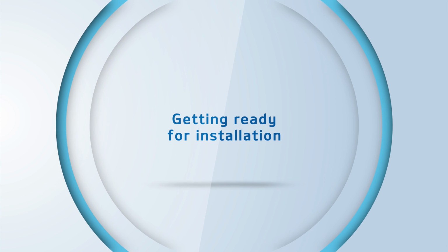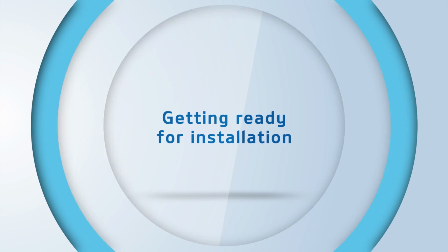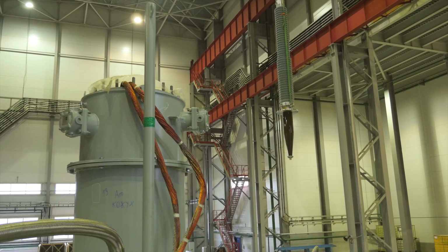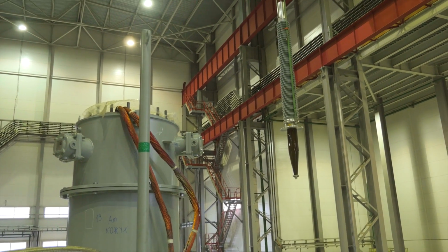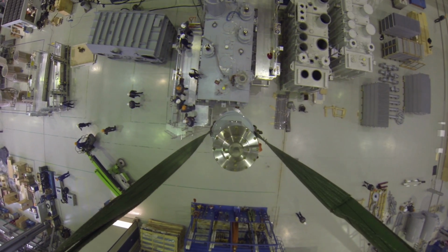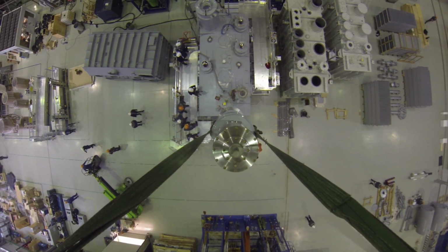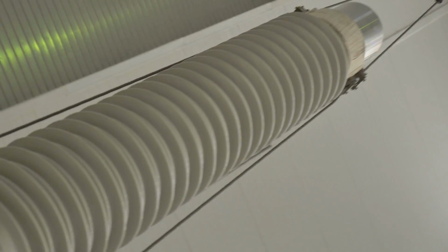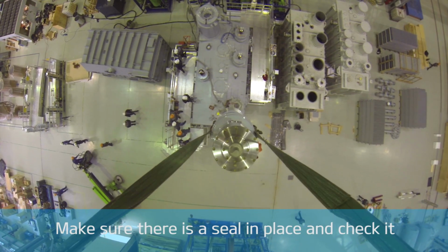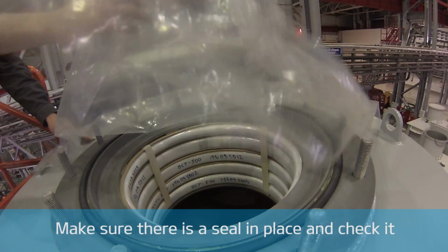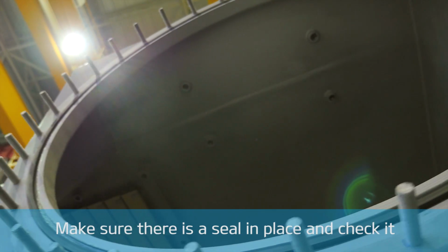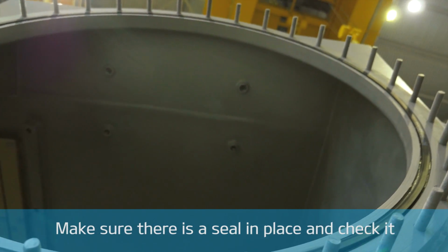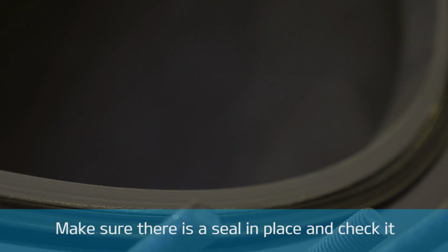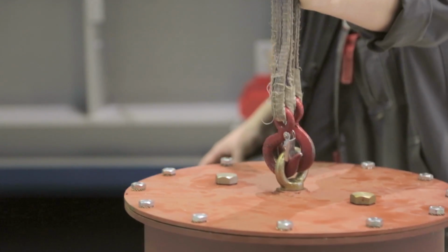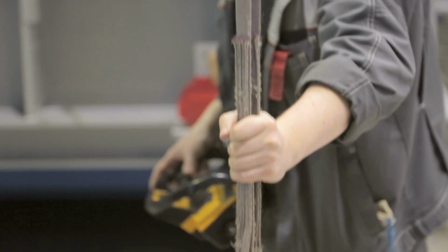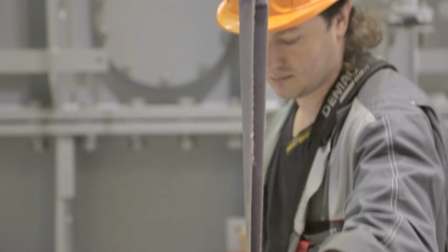Getting ready for installation. After all required measurements are done and on condition of the bushing conformity with the product certificate data, we can start installation of the bushing in a transformer. Prepare the mounting seat in the transformer. Make sure there is a seal in place and check it, making a replacement one if necessary. The installation process of bottom terminal bushings differs from that of a draw-lead type bushing. Hence, we're describing them separately here.